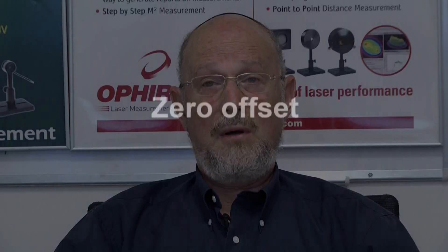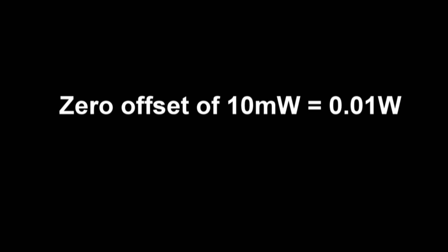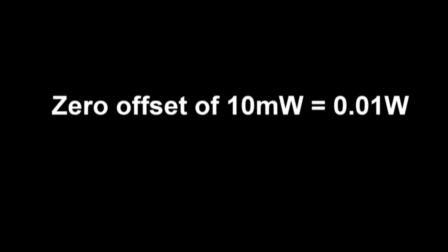Now in addition to that, we have another kind of error called zero offset. The zero offset becomes important when we're trying to read a very small value. What is zero offset? It means that even if we put no input into the meter, we get a reading even so. Now that could be because of external heat sources or the fact that the meter was not zeroed properly. Now let's say that there was a zero offset of 10 milliwatts, 0.01 watt.